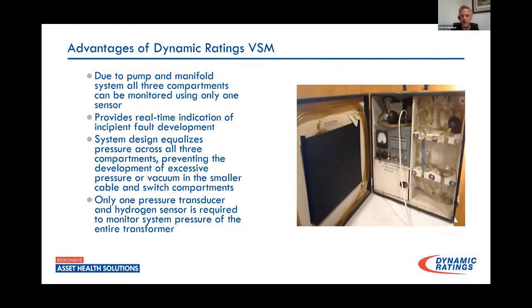And we used this for years. I was with the utility, like I said, in the field. I was actually doing this testing myself probably for 15 years of my career. And it was a fairly effective test. We would find problems quite frequently, and it saved us a few times on some that could have been a major problem. The only thing being with this is there's really no way to do this to the cable compartment due to the design of the transformer, and it not being pressurized. And that's where most of our failures were happening. We did find some main tank and switch issues using this test.